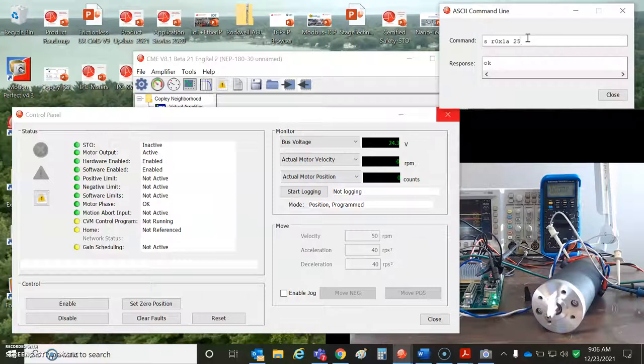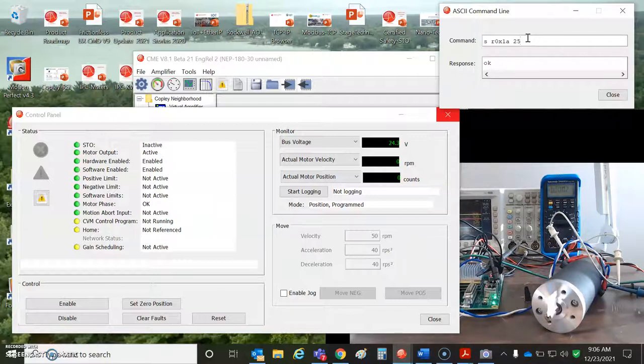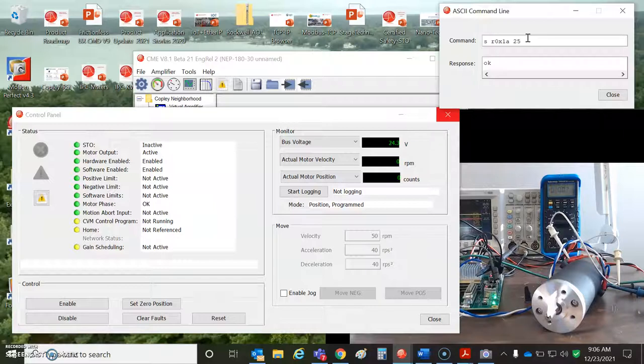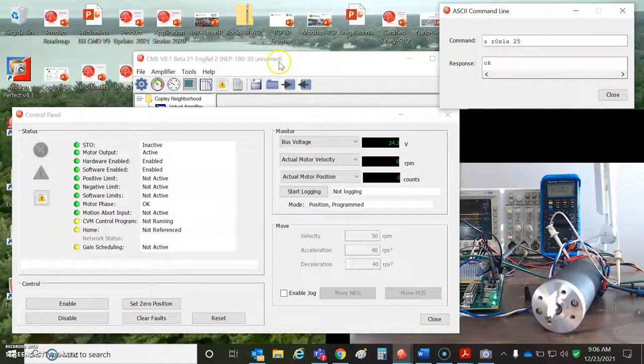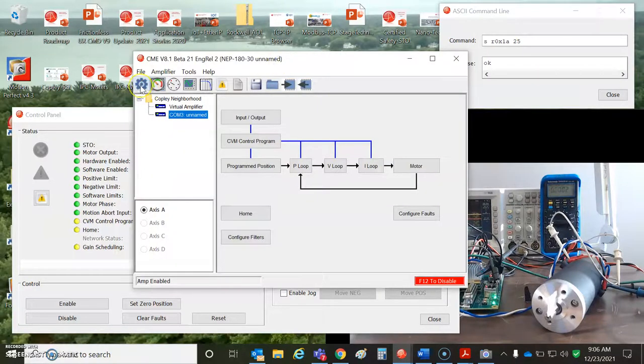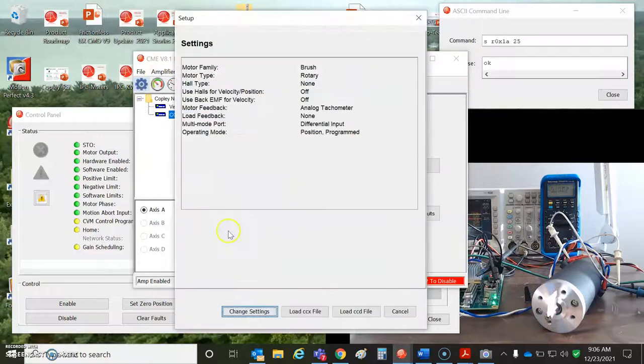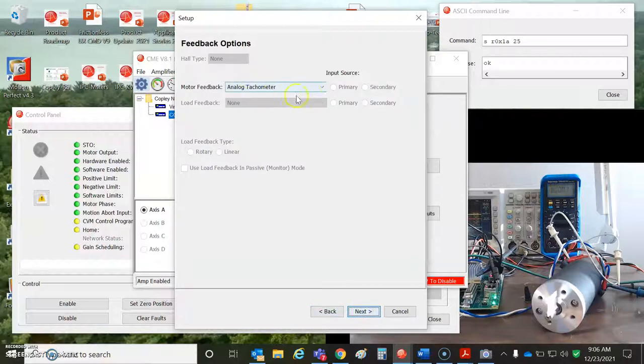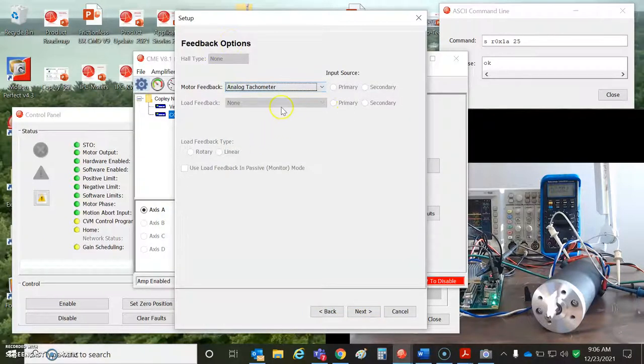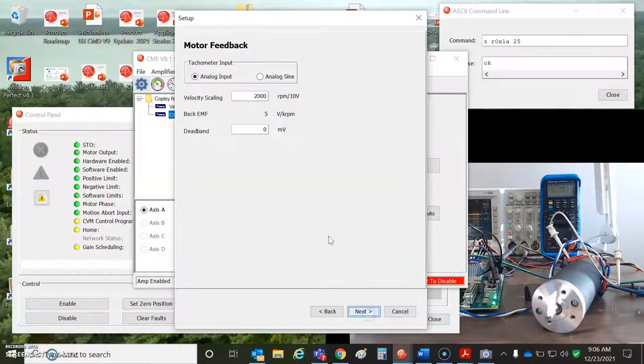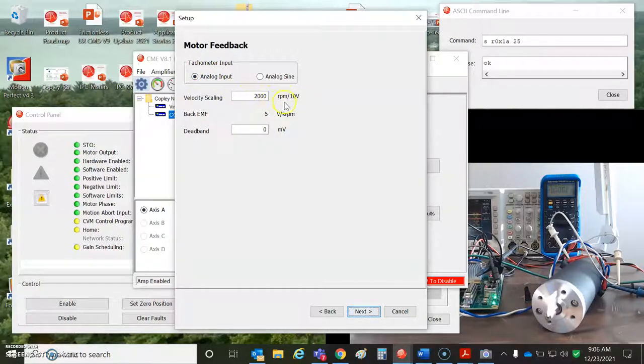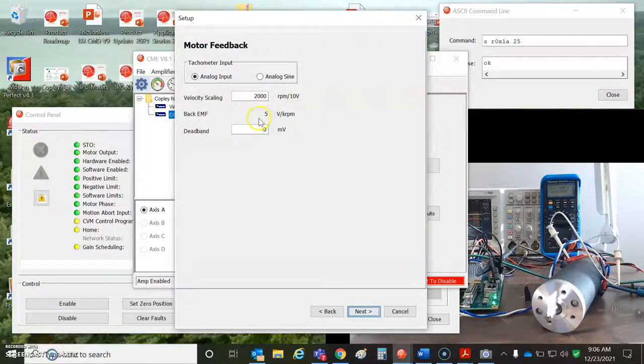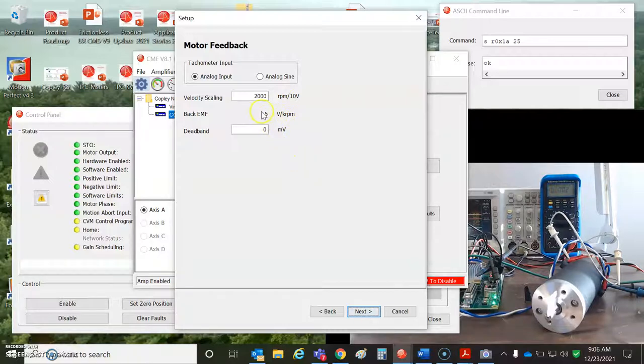If you let it sit here overnight or for the weekend, when I came in over a few days, it had rotated a bit. So there's a little bit of, it's only a 16-bit. So you're down to one quantum of a 16-bit A to D on this. But let's go through the basic setup here. How do we get this ready for tuning? Basic setup. This is a DC brush motor with a tachometer. We should have a position on the load, but we'll add that to the software later. I'm using the analog input and I'm saying at 10 volts, it'll be 2000 RPM based on the tachometer scaling, which I don't know. They're telling me I got five volts per K RPM, but I question that.